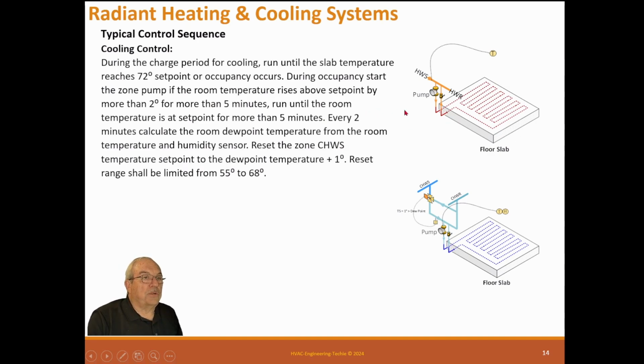During the charge period for cooling, run until the slab temperature reaches the 72 set point or occupancy occurs. During occupancy, start the zone pump if the room temperature rises above set point by more than 2 degrees for more than 5 minutes. Run until the room temperature is at set point for more than 5 minutes. Every 2 minutes, calculate the room dew point temperature from the room temperature and humidity sensor. Reset the zone chilled water supply temperature set point to the dew point temperature plus 1 degree. Reset range should be limited to 55 to 68.